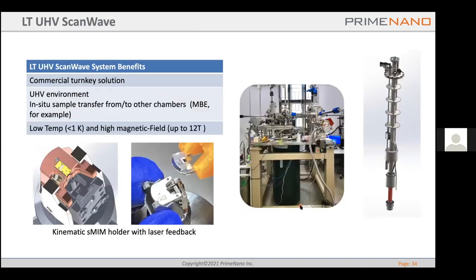And for the UHV system, we have the low temperature UHV scanwave system. It's a different system, in which the sMIM is integrated into the UHV condition and connected to other chambers, for example an MBE chamber. People can grow the sample in this MBE chamber and, in the UHV environment, transfer it to the sMIM chamber and cool down to low temperature with a magnet to do the AFM and the sMIM measurement. We also have a load lock, so you can load other samples and do a quick sample and probe exchange.